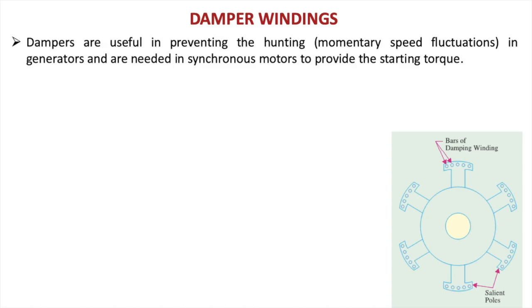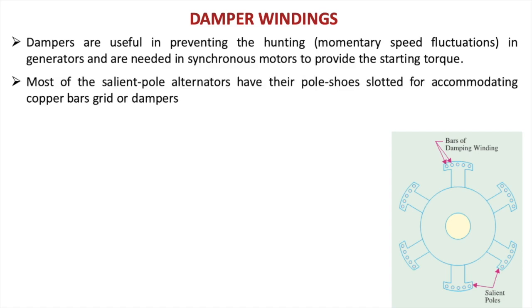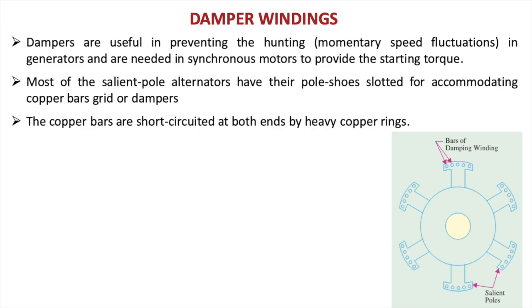Now come the damper windings. Normally on salient pole machines, damper windings are provided. The reason is that dampers are useful in preventing hunting, that is, momentary speed fluctuations in generators, and are needed in synchronous motors to provide the starting torque. So when it is a synchronous motor with salient poles, it will give you the starting torque and therefore it can run at the synchronous speed. Most salient pole alternators have their pole shoes slotted for accommodating copper bar grids or dampers. The copper bars are short-circuited at both ends by heavy copper rings.